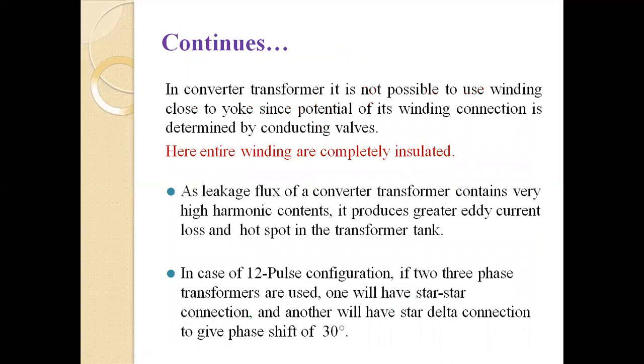In a converter transformer, it is not possible to use winding close to the yoke, since the potential of its winding connection is determined by the conducting valves. Here, the entire winding is completely insulated, as the leakage flux of the converter transformer contains very high harmonic content. It produces greater eddy current loss and hot spots in the transformer.